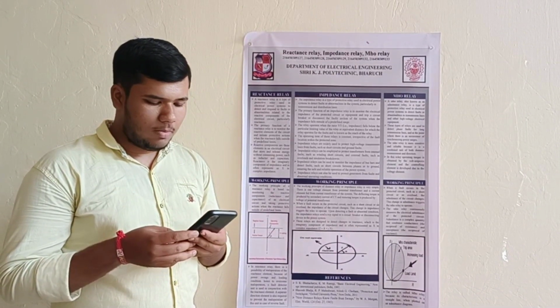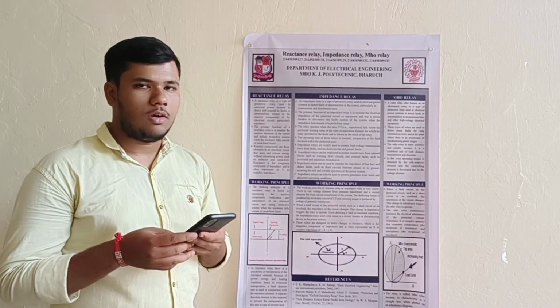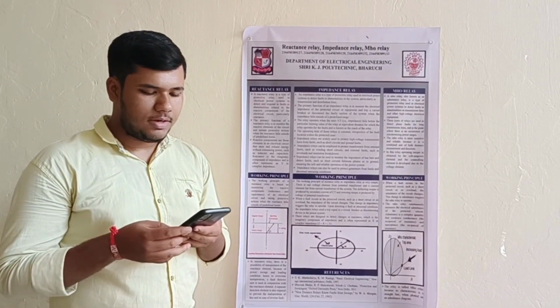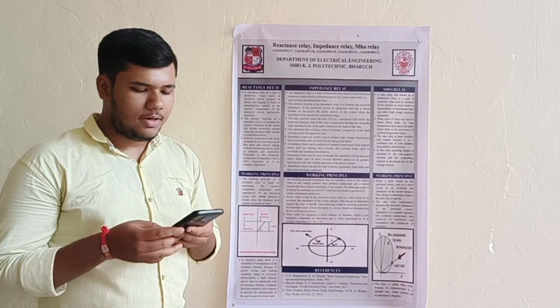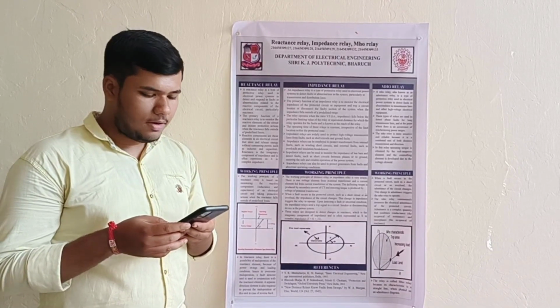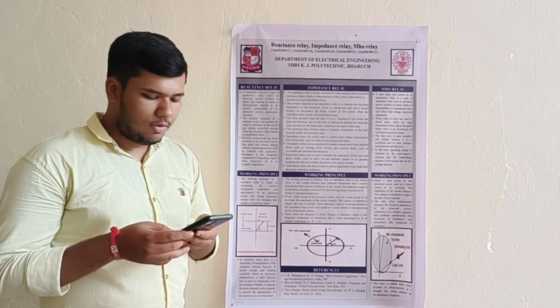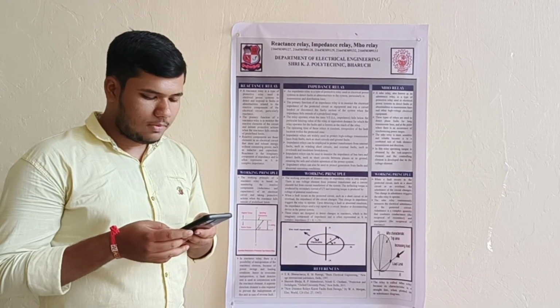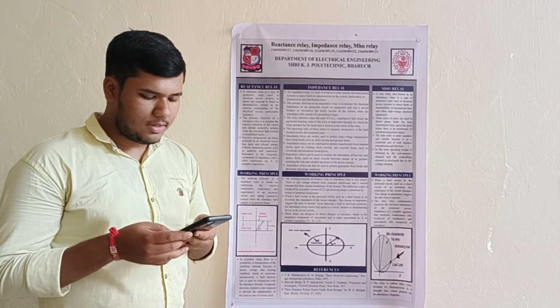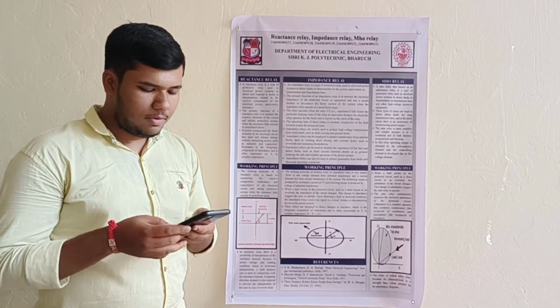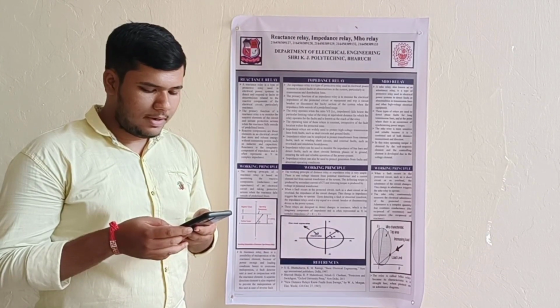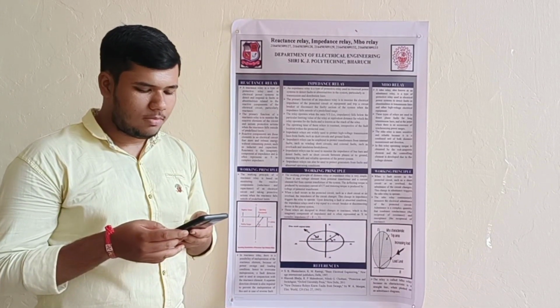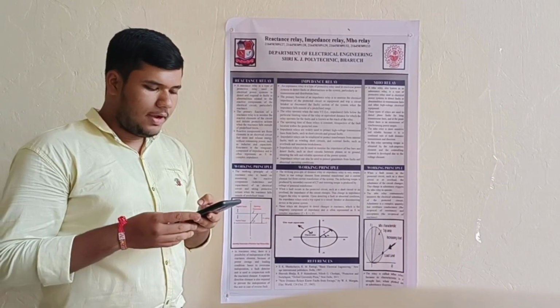Reactance relays are commonly used for protection of transmission lines and generators. They are effective in detecting faults such as short circuits, overload, and ground faults. By quickly isolating the faulty section, reactance relays help prevent further damage to the equipment and ensure the safety and reliability of the power system.